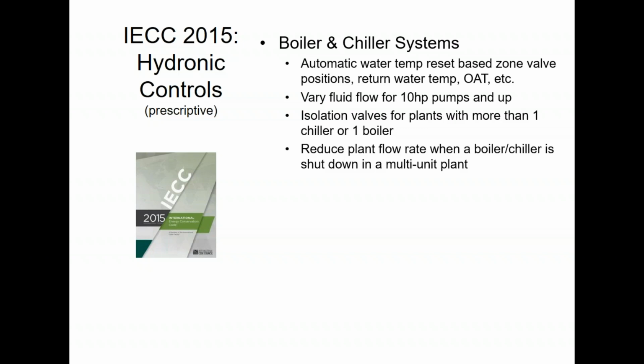All right, hydronic control systems, boiler and chiller type plants. There are specific controls you have to have on some of these. I mentioned the outside air reset already. Same thing on the chiller systems. You have to do the same kind of thing. You cannot provide the same chilled water temperature all the time. You have to have something that changes the chilled water temperature. And they give you some options in the code. You can do it based on zone valve positions. If none of your zone valves are 100% open, that obviously means they're all being overserved. So you should be able to reduce it, right? Based on return water temperature, you can do it based on outdoor air temperature, or whatever schemes you want to come up with. But the chilled water and boiler water temperature have to be reset.